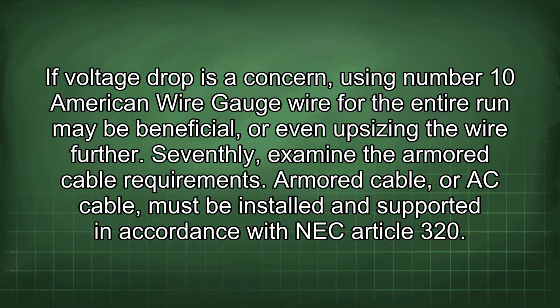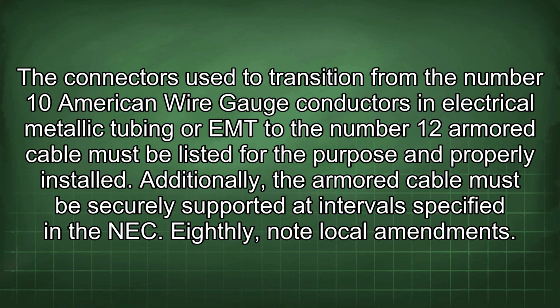Seventhly, examine the armored cable requirements. Armored cable, or AC cable, must be installed and supported in accordance with NEC Article 320. The connectors used to transition from the number 10 American wire gauge conductors in electrical metallic tubing, or EMT, to the number 12 armored cable must be listed for the purpose and properly installed. Additionally, the armored cable must be securely supported at intervals specified in the NEC.